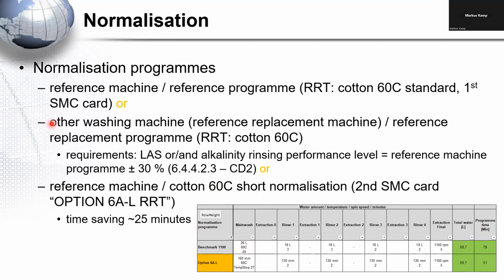For all who are running these tests regularly, a replacement machine is helpful, because then you don't stress the reference machine so much with all these normalization programs, where, as John explained, you have the threads, and the threads block the drain valve, or are lying on the heating elements and changing the behavior of the machine. So for most labs, it's very common to use a replacement machine. Maybe you have two of them, so you don't stress your reference machine so much, which has only to be run for the reference program for the washing performance or cleaning performance.